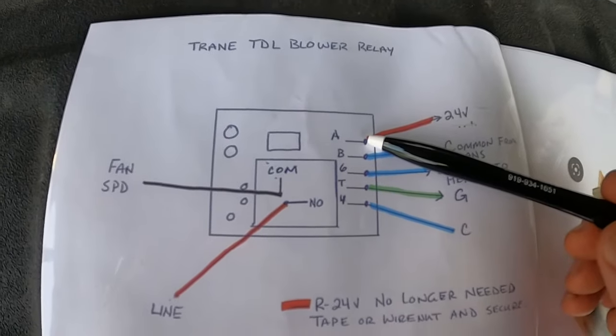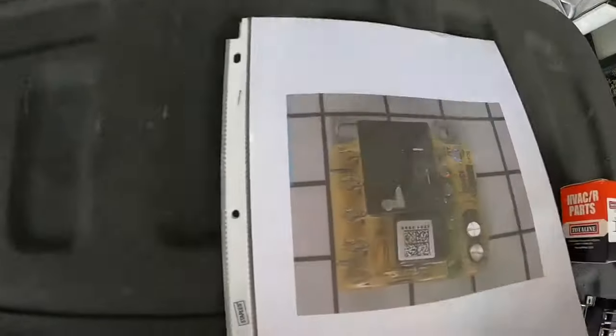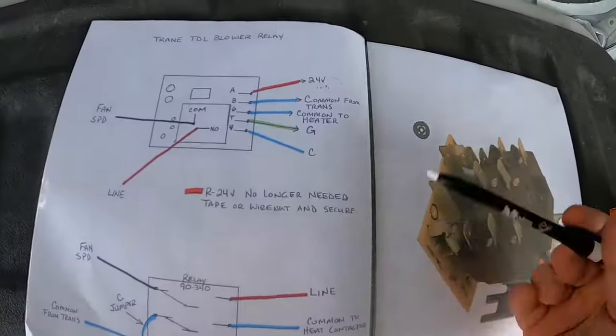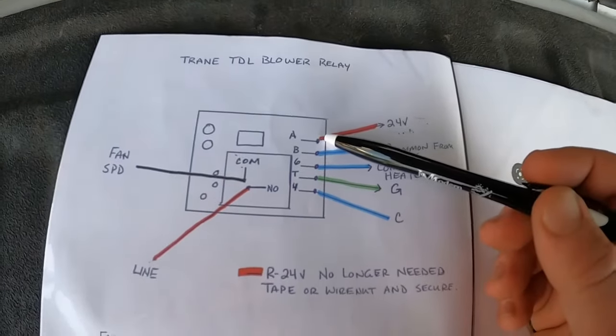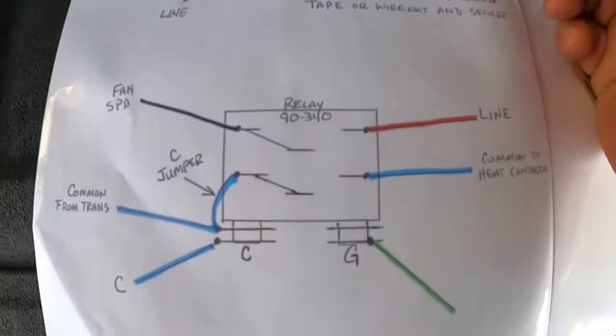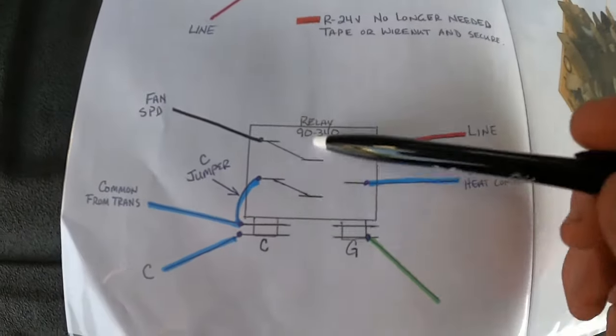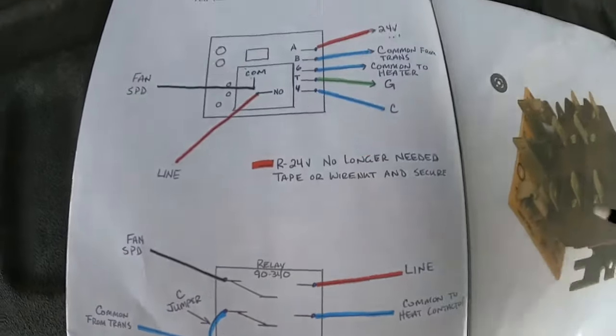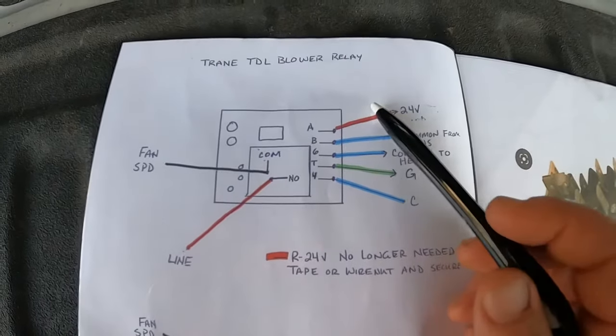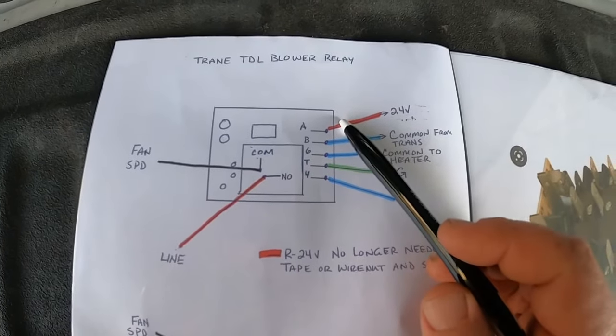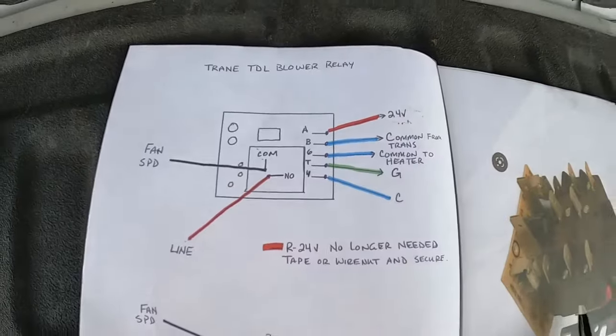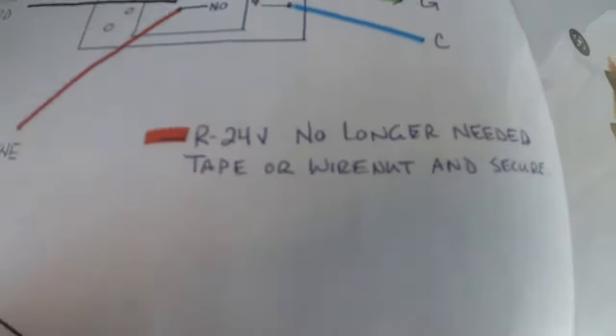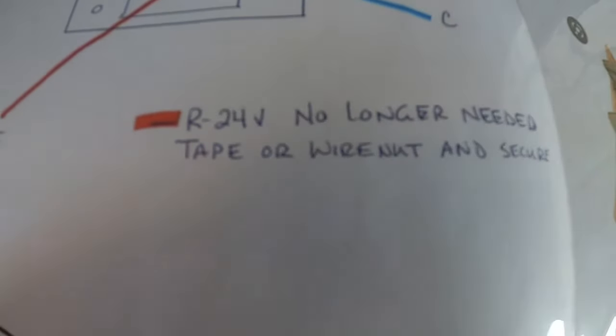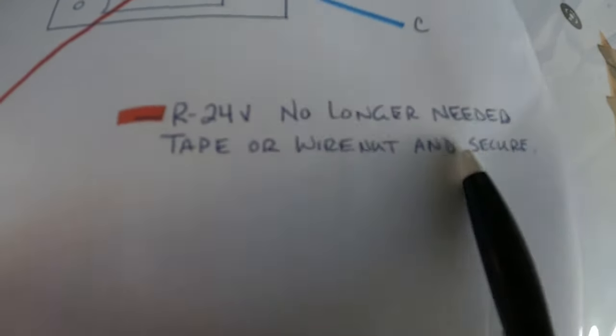First of all, you've got your 24 volt. Now this is for this particular relay. This just powers the timer and the board. You don't need that anymore if you're going to put this relay in. And don't make fun of my drawing. I did the best I could. You can just simply unplug this one, cut the Sta-Kon off, stick a wire nut on it, and you're done with that wire. It tells you that right there. I give them the instructions. It's unused wire, tape it off, I prefer a wire nut.